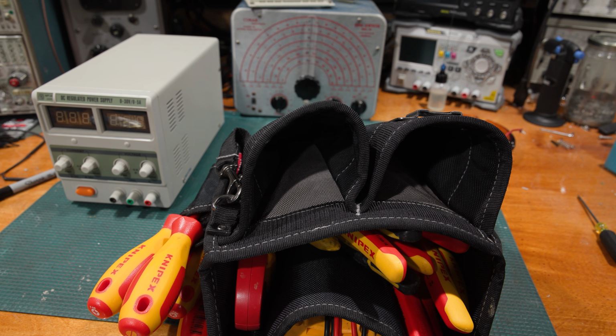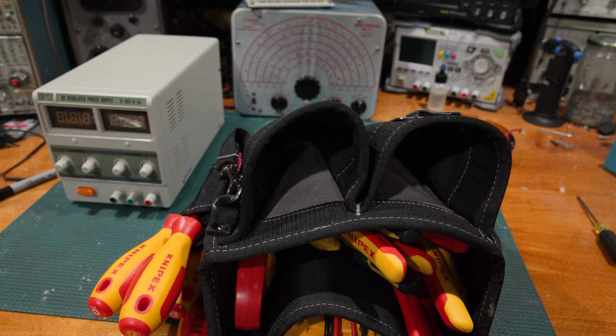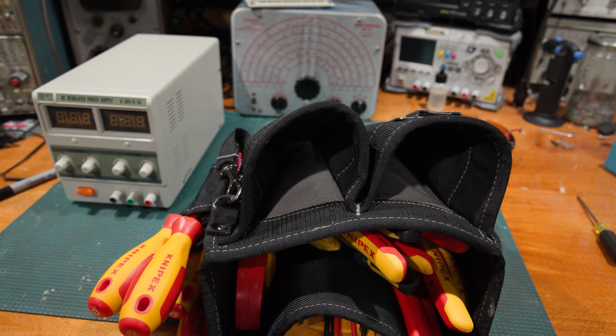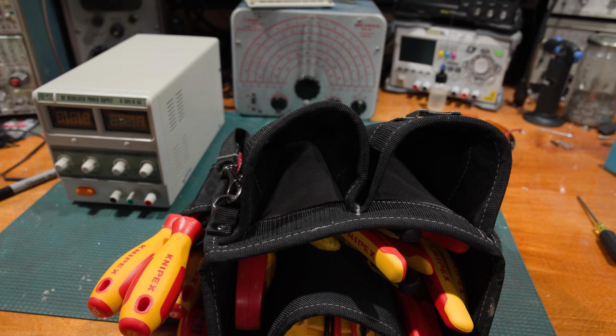The goal at the end of the day is I have two Fluke 5200As that need to be calibrated. We repaired both of those in a previous video. They're working just fine. Actually, they're still open on the floor off camera that way. I need to put some covers back on there and get them aligned and calibrated. They had some big power supply repairs done, things like that. So absolutely, they need a bit of calibration and adjustment.